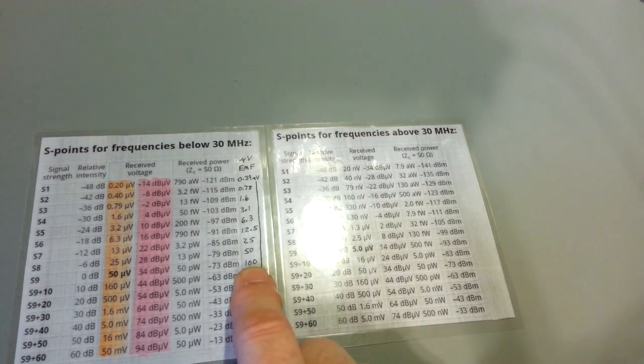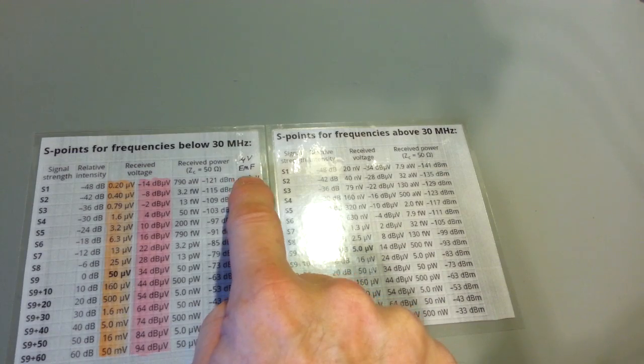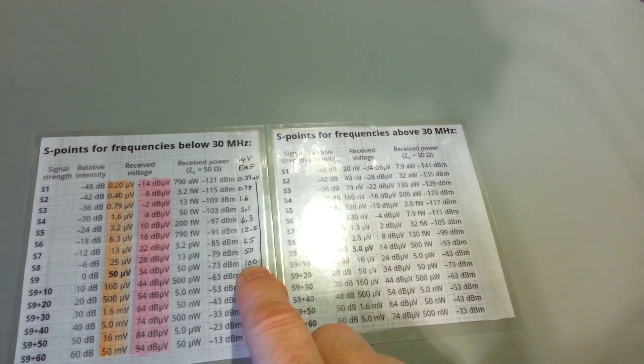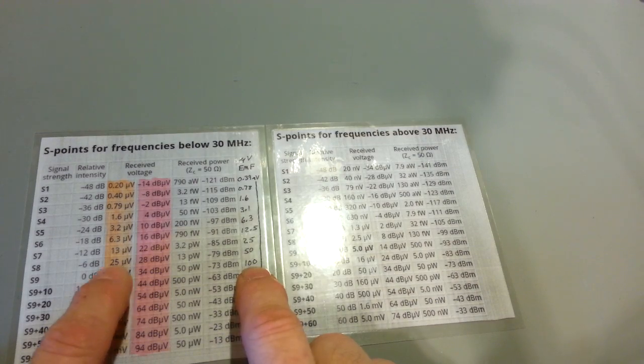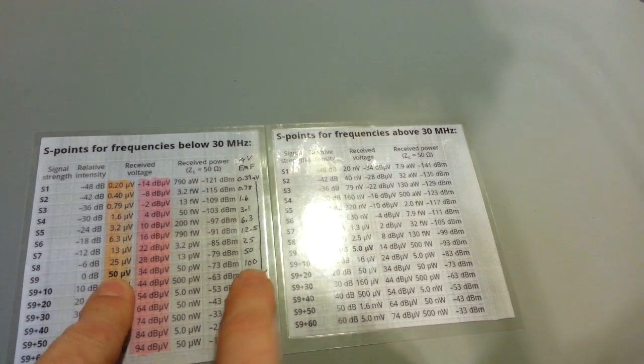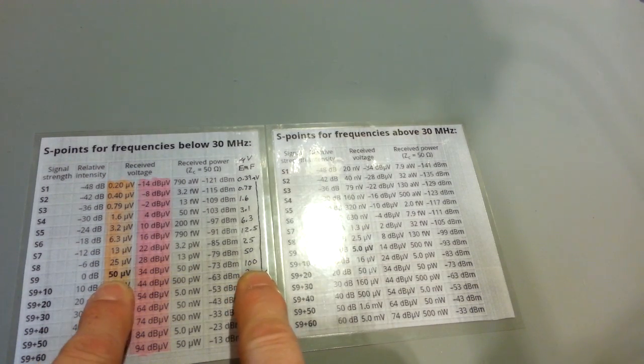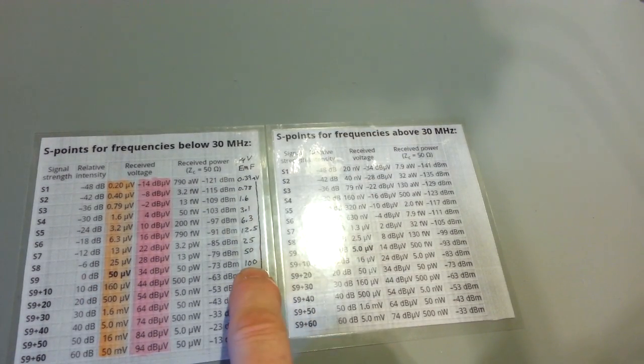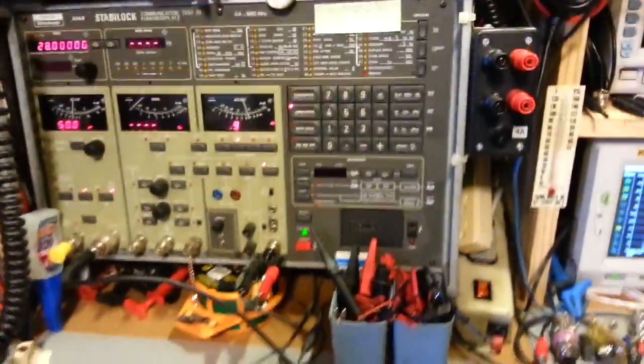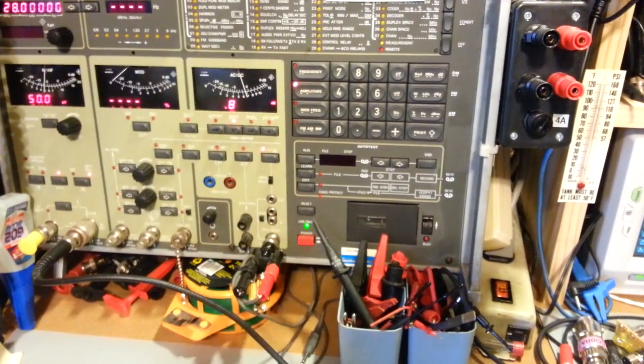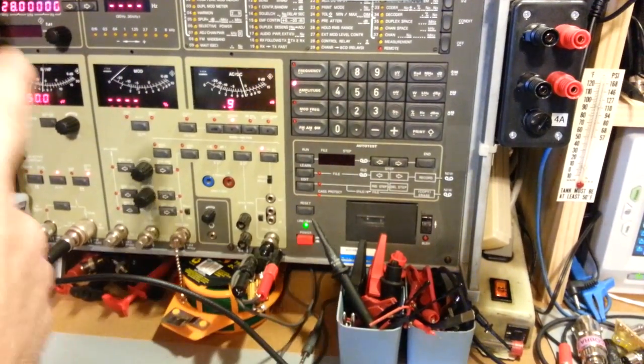But this little handwritten column here, you'll notice that says, and remember, microvolts EMF, that's 100 microvolts. That's what's confusing for people. Which one is it? Is it 100 or is it 50 microvolts? Well, as you can see on this chart here, the answer is yes. And the answer is yes to both of them. It is 50 and it is 100 microvolts. The difference is this measurement here is with no load. This is with 50 ohm load. That's the difference. Now, if we look at the communications test set here, this one actually demonstrates that very well. And it does all of these different measurement types. So I currently have this set up at 28 megahertz.